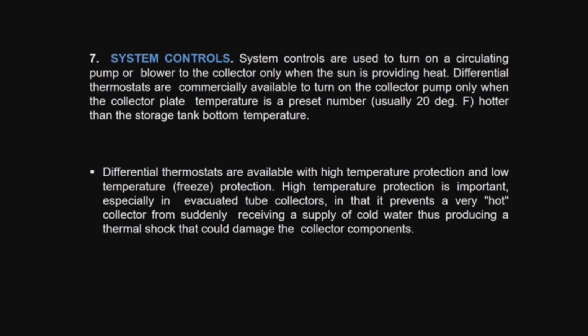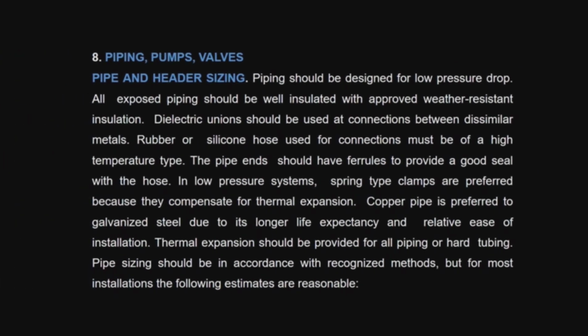Differential thermostats are commercially available to turn on the collector pump only when the collector plate temperature is a preset number, usually 20 degrees, hotter than the storage tank bottom temperature. Differential thermostats are available with high temperature protection and low temperature freeze protection. High temperature protection is important, especially related to the collector, in that it prevents a very hot collector from suddenly receiving a supply of cold water, providing a thermal shock and damaging the collector components.